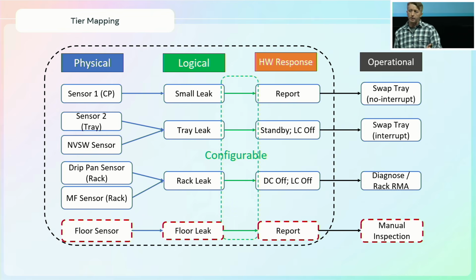As you scale and end up with more and more hardware, and the risk of an unintended system developing a leak increases, you want to get more conservative. You want to make sure if there's a leak, you shut down, keep people safe, keep material safe. This is something we configure in the RMC and in the tray. It almost certainly changes over time and can vary between products.